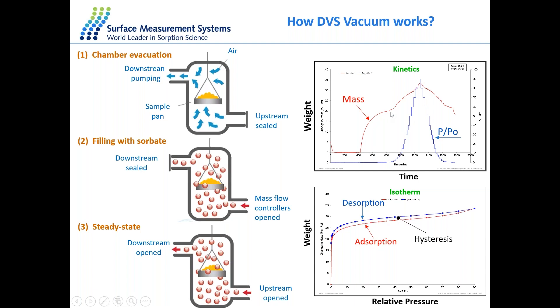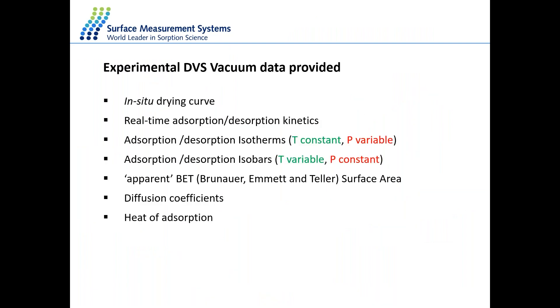Equilibrium points at different pressure steps can be reached in time mode or DMDT (dm/dt) mode. Most often we collect data in DMDT mode, setting a certain equilibrium threshold value — when this threshold is met, the software automatically proceeds to the next stage. The system allows collection of important in-situ data: outgassing curves, real-time adsorption-desorption kinetics, and adsorption-desorption isotherms. From kinetic data and mass equilibrium points at different relative pressure steps, we calculate the isotherms. We can also collect adsorption-desorption isotherms at different temperatures to calculate heat of adsorption and kinetic diffusion coefficients.